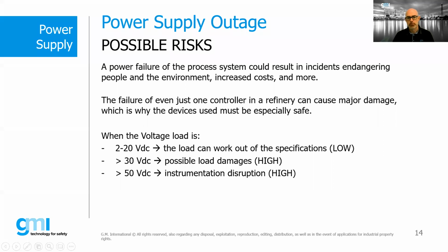The redundancy of a safety power supply system minimizes this risk because common mode failures are considered in the SIF calculation, necessary to get the certification for a safety related device. The second dangerous failure condition of a power supply system is when the output voltage reaches a value higher than 30 volts. In this condition, the load is subjected to extra voltage, which can damage it. Or, in case of output voltages higher than 50 volts, the field instrumentation can suffer a definite disruption.